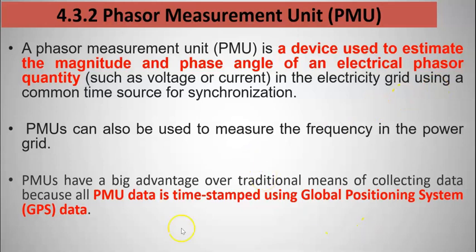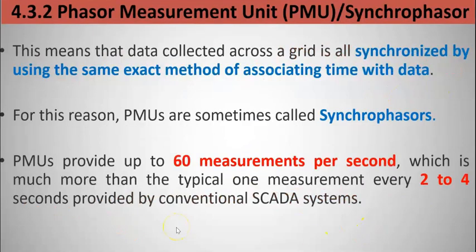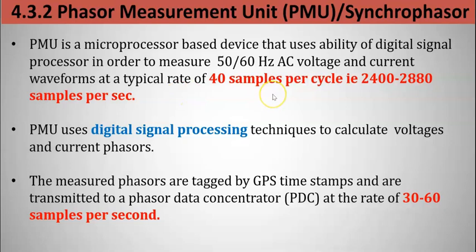As given in the description, the sampling rate of PMU is very important, 40 samples per cycle. But nowadays in modern systems it has gone up to 120 also. Not only PMUs are considered, but micro PMUs, which are very fast, are also coming up, especially in the distribution system. Micro PMU is used in distribution, and PMU in transmission, though we just call it PMU for distribution too - that's the latest concept. So the rate has gone very high, imagine 40 samples per second, how fast PMU is working.